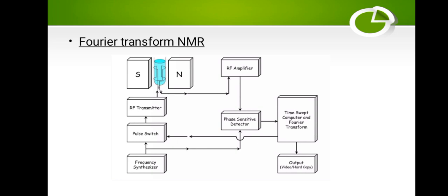A short pulse of radiation is applied to the sample and the magnetic field is scanned. If the signal due to water is suppressed, there is initial saturation at the water frequency which is diminished by addition of deuterium oxide. Before another test can be taken, the sample must be allowed to relax. During this period, further saturation of the water signal can be done and the process repeated many times. The sequence of events, data collection, and operation of the NMR spectrometer is automated.